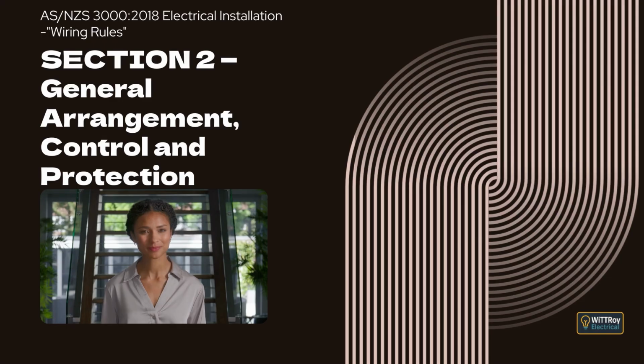Clause 2.4.4, Auto-reclose devices. This clause explains when auto-reclose devices are allowed. An auto-reclose device may be used if several important conditions are met. First, it must not be used as the main method of fault protection required by Clause 1.5.6. Second, the auto-reclose must not operate after someone has manually switched the device off. This prevents unexpected reconnection while someone is working.